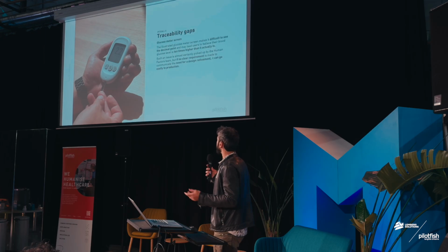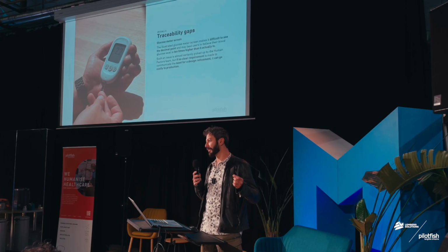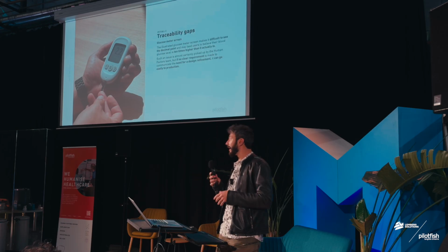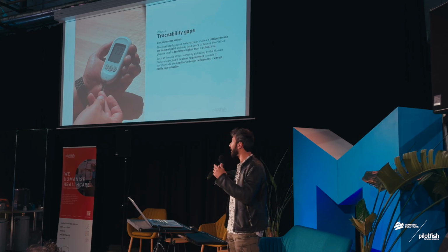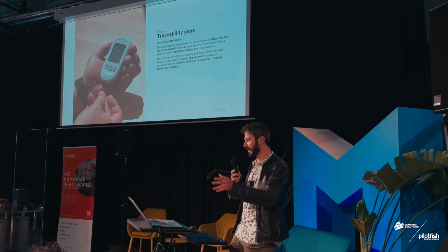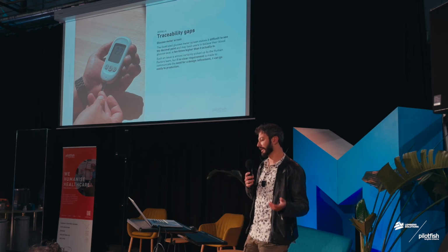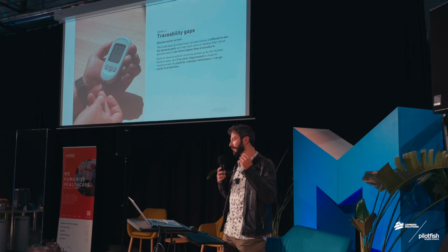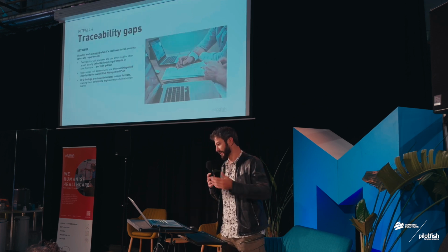Now, the fourth one is a glucose meter. And if you look at it, you might see 2.2 millimole per liter, you might see 22, and this already points to the direction of, okay, this is quite misleading if it's not entirely clear, even though it has the sole purpose of communicating this amount, and you can imagine a tenfold difference between the delivered amount is quite critical.